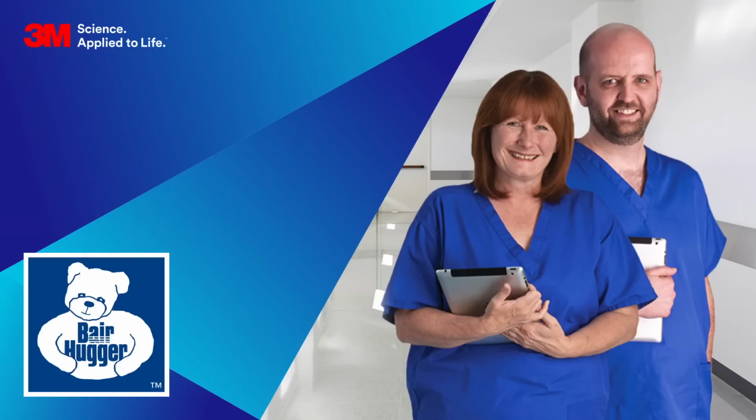So Helen, another commonly asked question we have is, can I use an arm support with the model 545 adult underbody blanket? You can. It's actually designed for patients where their arms are down by the sides or above the head. Basically, you don't want to occlude the flow going round the blanket itself. So if you need proper supports in where you're going to be occluding the flow, then you're better off using a 635 blanket instead. So Danny, a question that we got on Facebook was, will excess fluids used during the procedure pool on the underbody blankets?